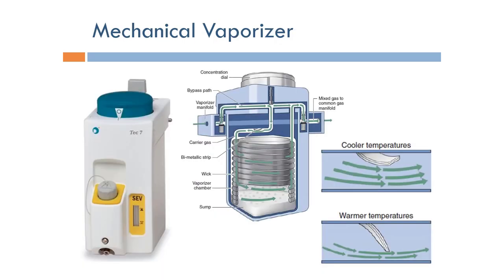Vaporizers can be implemented either mechanically or electronically. The mechanical vaporizer relies on a mechanical device that does not require any power. It takes the input fresh gas and divides it between a bypass path and a path that goes over the inhalation anesthetic. The portion going through the anesthetic picks up a high concentration of anesthetic vapor and then mixes back with the bypass portion, and the summation of the two gives us the concentration that we need.